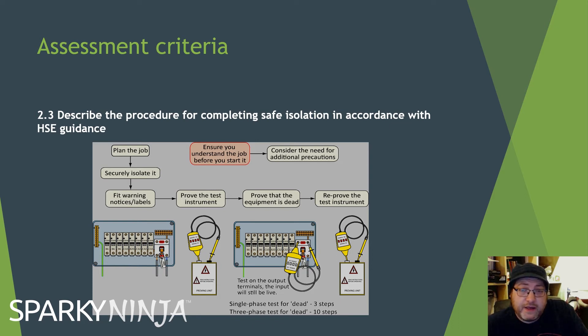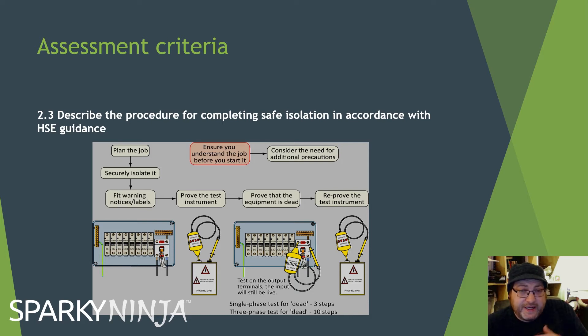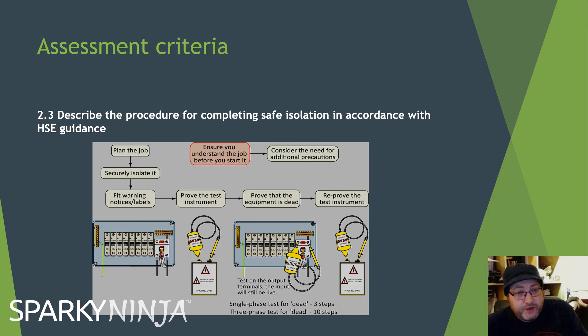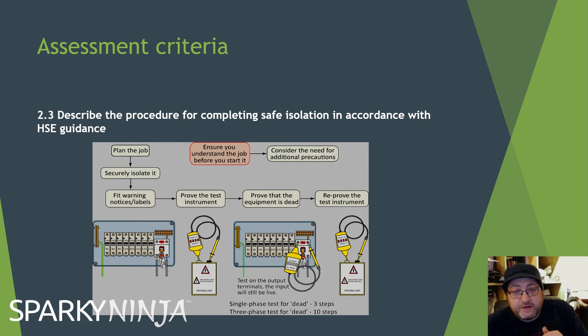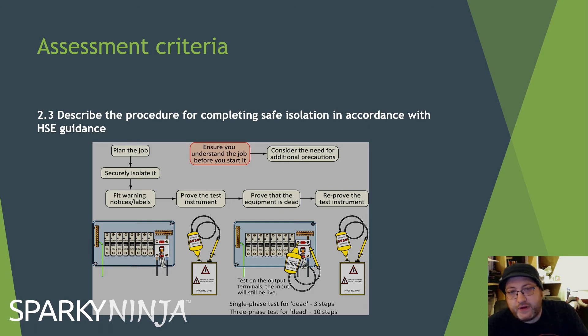The key thing is whether it's single phase or three phase. For single phase, there are three terminations to test: line to neutral, line to earth, neutral to earth. For three phase, there are ten: neutral to earth; line one, two, and three to neutral; line one, two, and three to earth; then line-to-line combinations — line one to line two, line one to line three, and line two to line three. Ten in total.